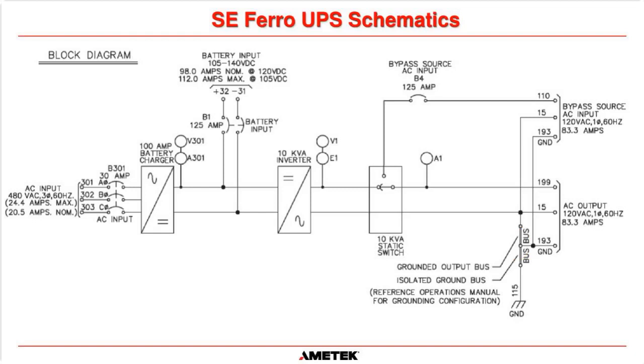The only thing I didn't mention here was we also have a bypass source AC input breaker. So that is a way we can disconnect the bypass source if we have to. So that is a breaker on the front of the system. So there's 3 breakers on the front of the system: B301, B1, and B4. B301, this one here, is for the AC input. B1 is for the battery input. And this one here is the bypass source AC input. Some people call it the dirty power or the alternate source. All 3 terms are interchangeable.